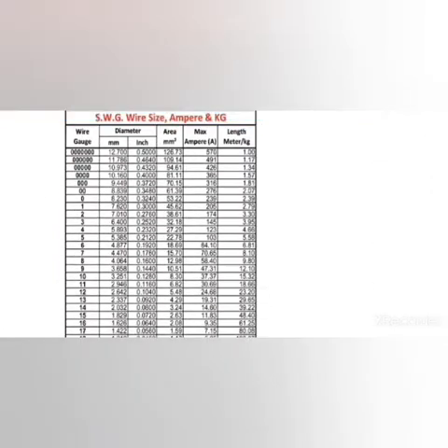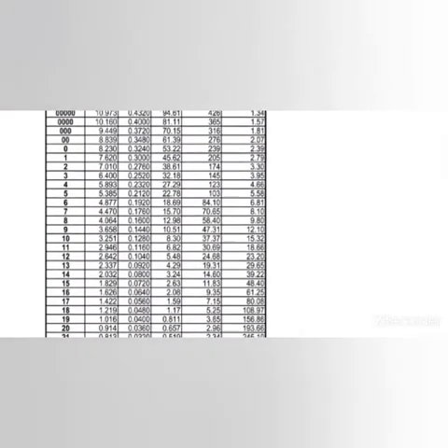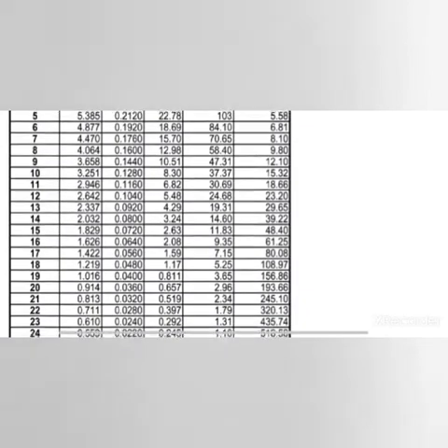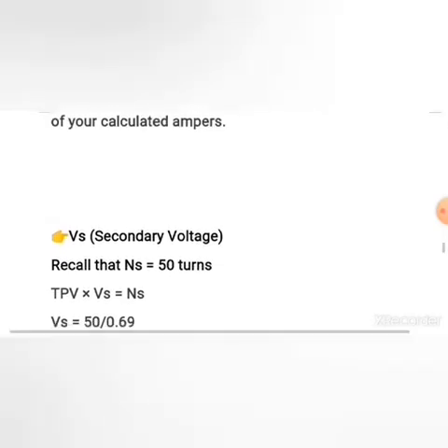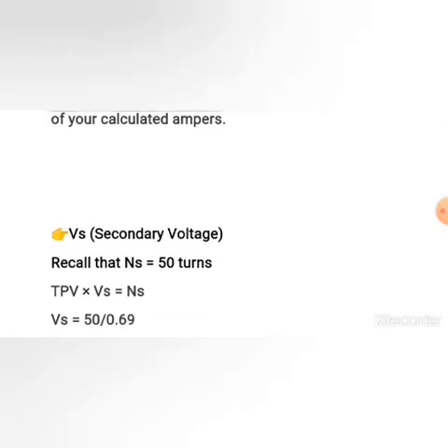We look at the maximum ampere column in the SWG table and check for the range of 7.8 amps. We can see SWG 17 gives 7.15 amps and SWG 16 gives 9.35 amps. This means we should not use any wire smaller than SWG 16 for the primary winding. Next is the secondary voltage.